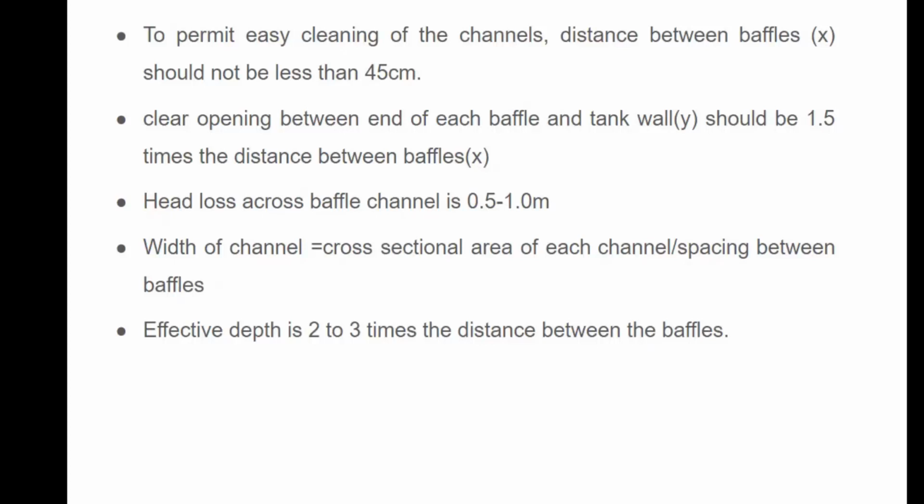Width of the channel: we can calculate the width of the channel by the cross-sectional area of each channel divided by the spacing between the baffles. Then the effective depth is 2 to 3 times the distance between the baffles. And the head loss across the baffle channel is 0.5 to 1.